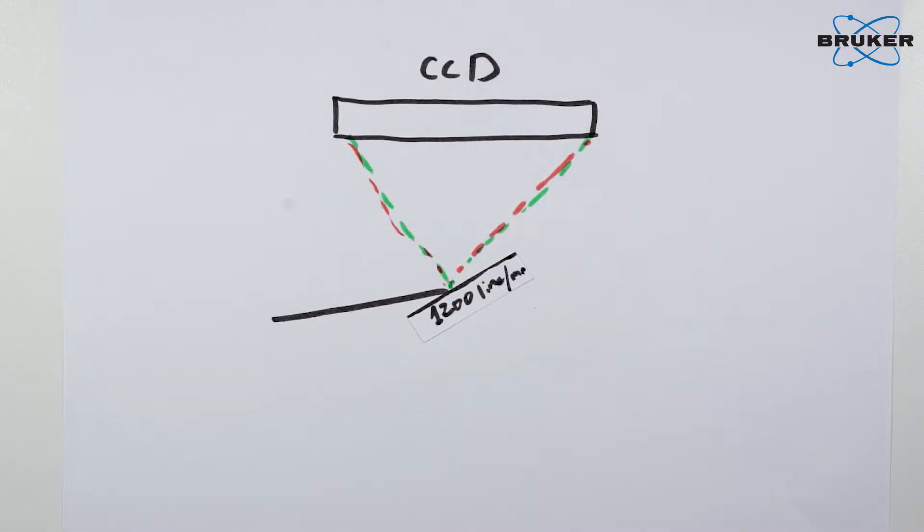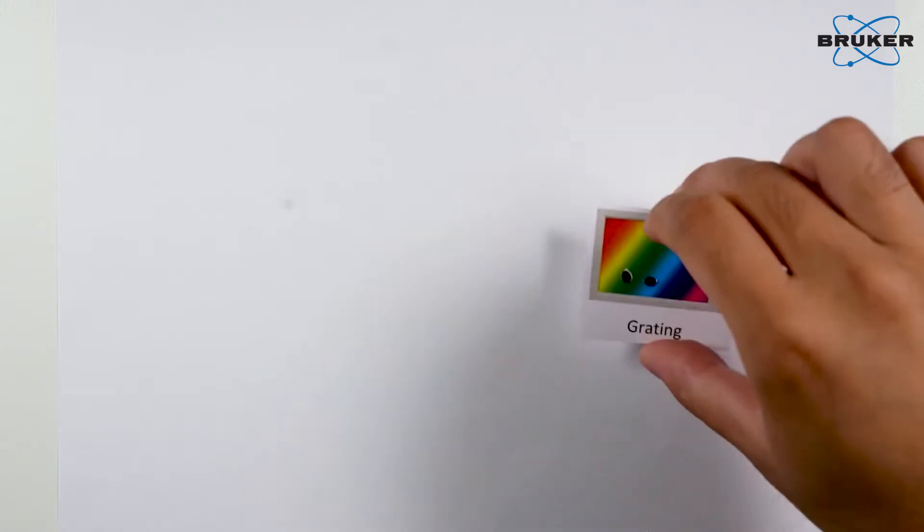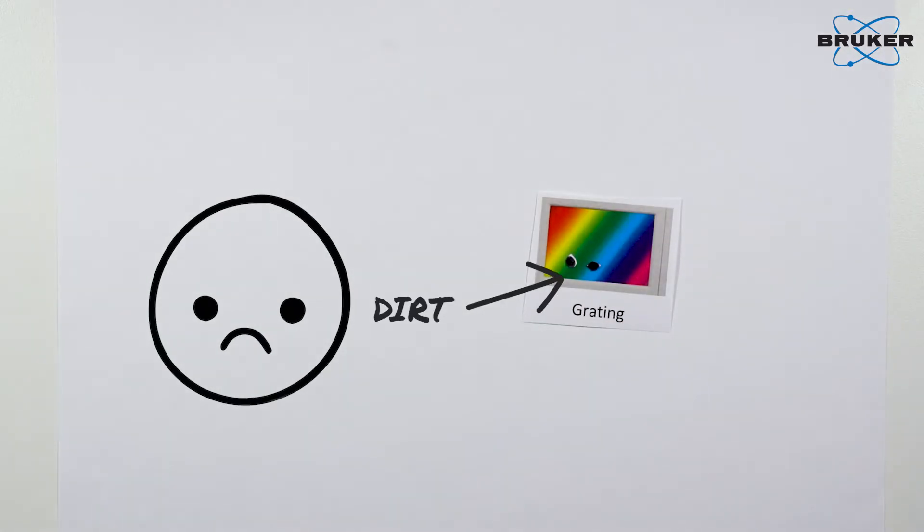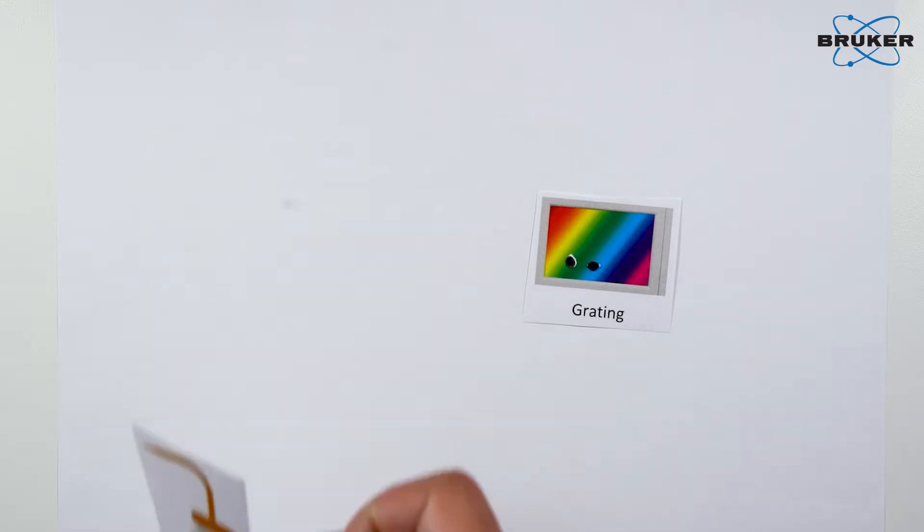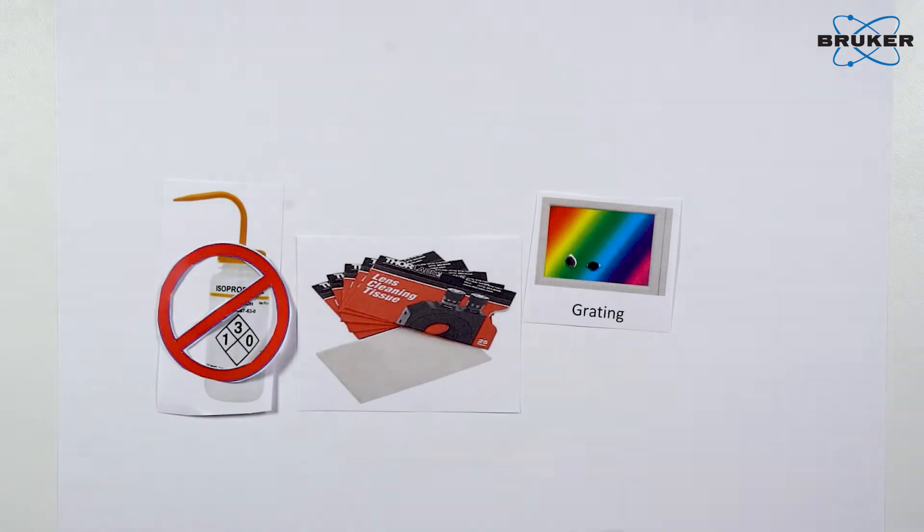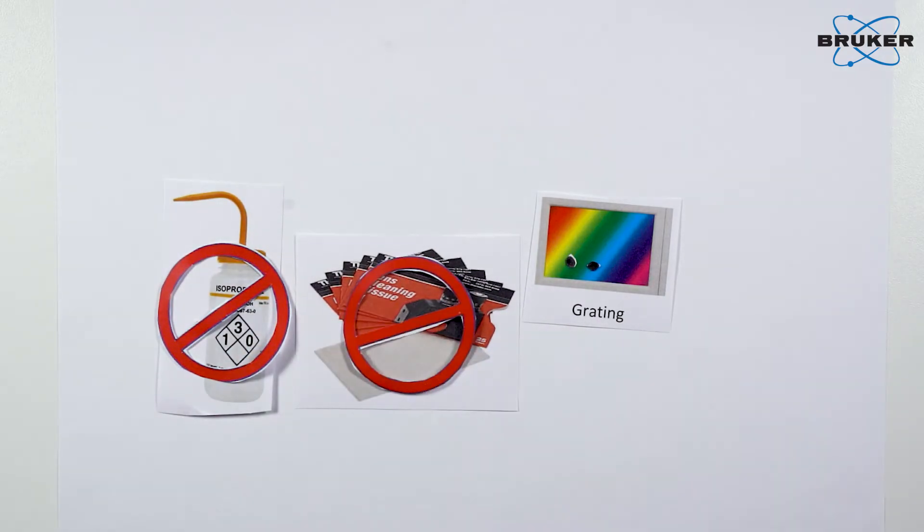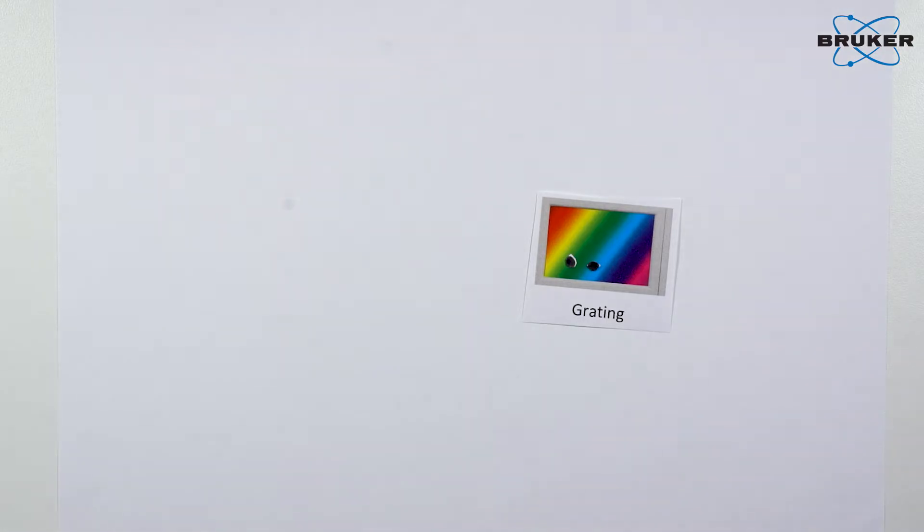Remember that you should always exercise a lot of care when manually handling the grating. Like any other optical element, a grating must remain clean to deliver the best performance. Under no circumstance should you wipe or use a solvent to rinse the grating, as otherwise the microstructure on the surface will be damaged.